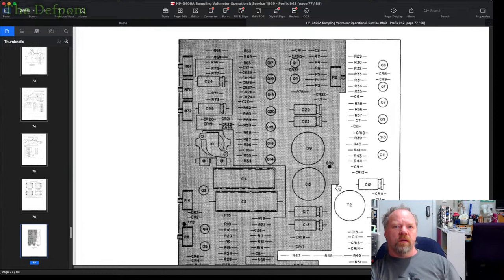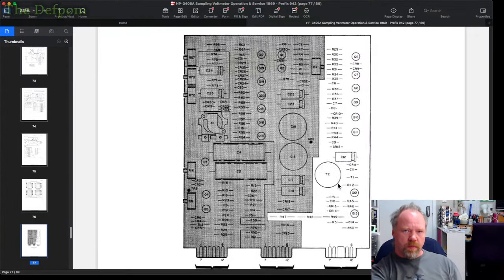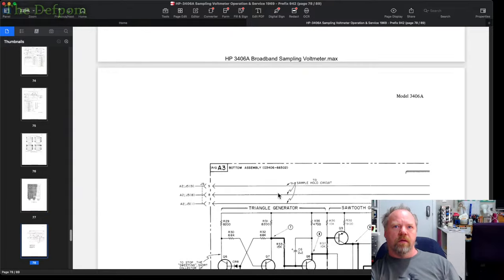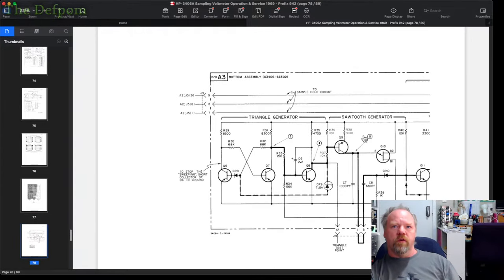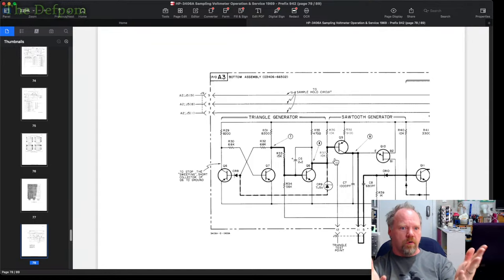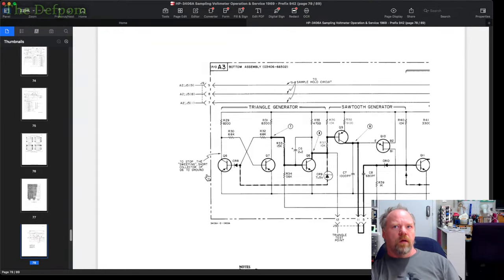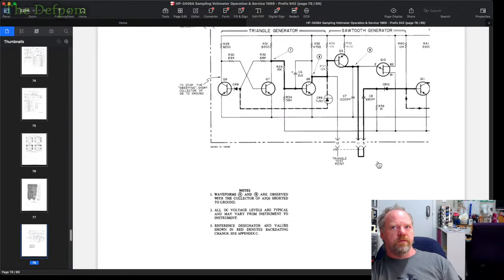Yeah, so this is the A3 board, it's the bottom board, which is basically power supply stuff and the pulser and stuff like that on it. Triangle generator, I mean, this is obviously working because it's generating pulses. Pulse sizes are about correct, like the pulse lengths and the pulse times, which I mentioned in the manual. Based on the example waveforms it's giving, I'll set the scope up for that waveform sample, and it looks right. So the pulser stuff seems to be working fine.